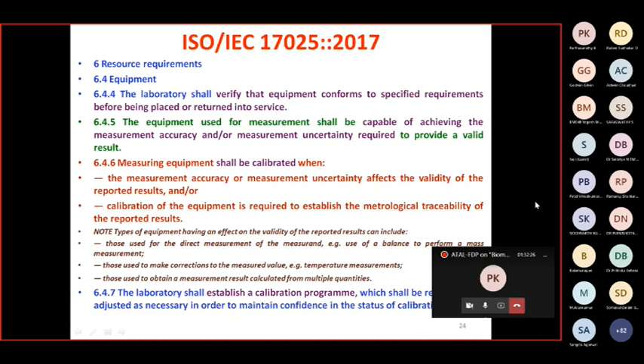But at the same time, a thermometer available to monitor the temperature of your laboratory or calibration center requires to be calibrated, because a calibration center has a specification of 20 degrees plus or minus 0.2 degrees. So any variation can affect the calibration result. So the thermometer used for measuring the temperature of a room in a laboratory requires to be calibrated. So what will you do? You will list down all the instruments and gauges which have to be periodically calibrated, and identify whether it is going to affect your test result or calibration result. If the answer is yes, they have to be put under a calibration program.